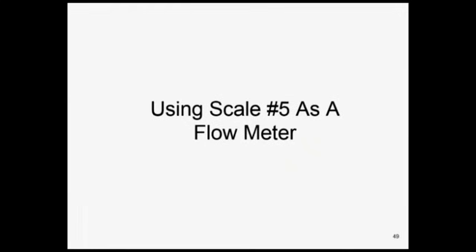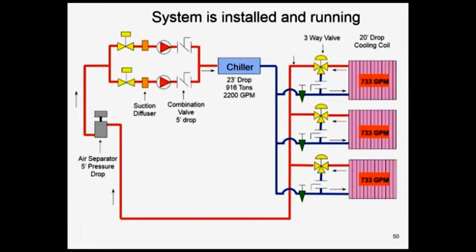Let's go back to the scale 5, that formula we talked about on a system sizer. Let's use it as a flow meter. What am I saying? Here's a simple sketch of an old-fashioned system with 3-way valves, and I've got a chiller on it. Let's say it's a 916-ton chiller. Let's leave it at a 10-degree delta T. Let's leave it at 2.4 GPM per ton. Those are the old numbers we want to use.